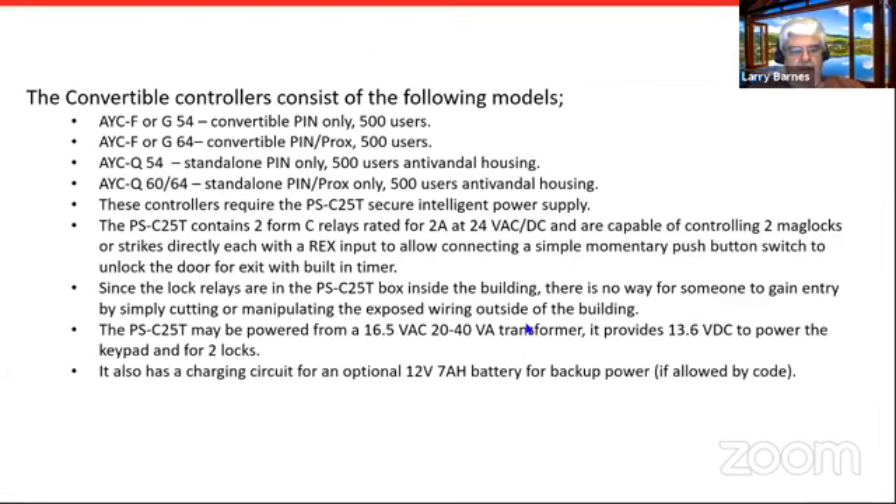Power for the PS-C25T is an external 16.5-volt transformer rated 20 to 40 VA. For a single lock and keypad, a 20 VA transformer would be more than enough. It has a power supply circuit that supplies 13 volts DC for use with mag locks and strikes, plus a charging circuit for an optional 12V 7 amp-hour sealed lead acid battery for battery backup — if that's allowed by code, as it's a no-no with mag locks in some places.